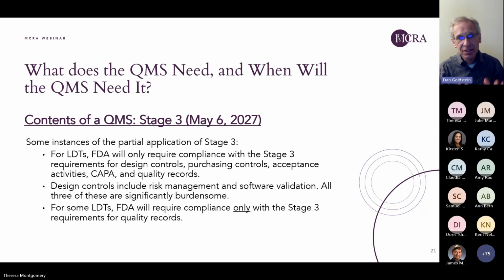Design controls, honestly, are a bear. FDA has a fairly strict and clear, but not short, procedure that you go through in creating a new design for a medical device or for changing the design of a device you already have. And remember, Jim mentioned that you may need to make a submission for a change to a device. Once it's a medical device, even if you don't have to submit the change to FDA, you still go through the process of design changes under design controls. And design controls include software validation, so that FDA guidance that I mentioned for software development, and the one for cybersecurity. And design controls under the FDA quality system regulation include risk management. So again, that international standard, 14971, will apply as well. So just having a short list doesn't mean that it's a small burden.